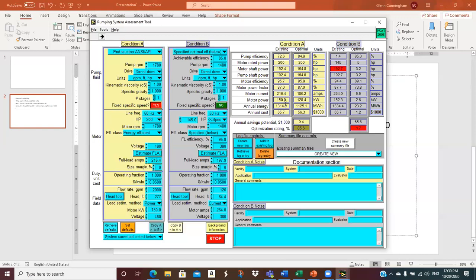And then this is the annual energy in megawatt hours. We got the operating fraction is 1. So this would be the motor kW. Let's see, we got motor rated power. Oh, out here, it's 150 times 8760 divided by 1,000 to put it into megawatt hours instead of kilowatt hours. So that's the annual energy, and then that's the cost at 5 cents, $65,700.